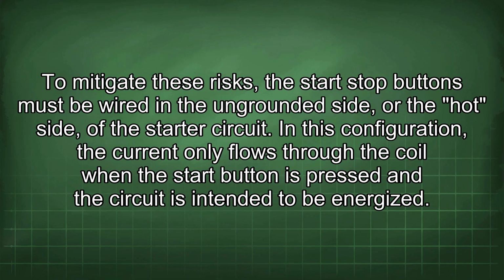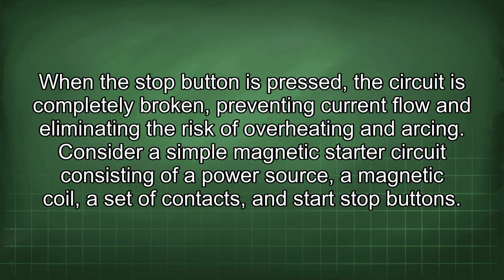To mitigate these risks, the start-stop buttons must be wired in the ungrounded side, or the hot side, of the starter circuit. In this configuration, the current only flows through the coil when the start button is pressed and the circuit is intended to be energized. When the stop button is pressed, the circuit is completely broken, preventing current flow and eliminating the risk of overheating and arcing.